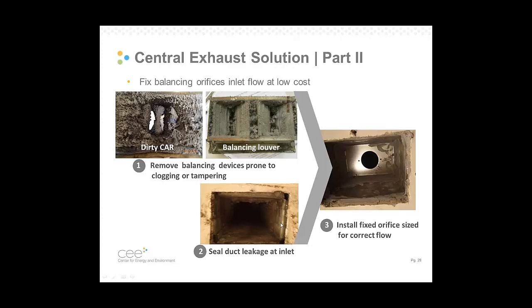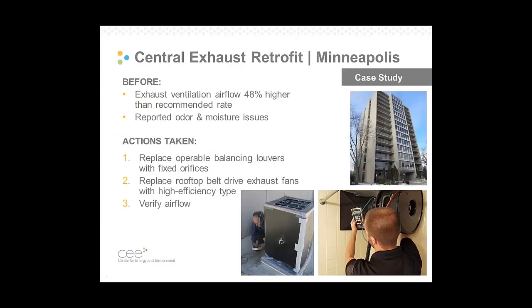This is the other detail we're handling at the inlet, which is just air sealing the duct here where it meets the ceiling. This is right after you take off the register cover. You'd see maybe some gaps between the ceiling drywall and the duct. We seal them to make sure that all the air that's drawn up into the duct is from the apartment unit and not from unintended places like ceiling and wall cavities. Again, you can see that this has been sealed with mastic.